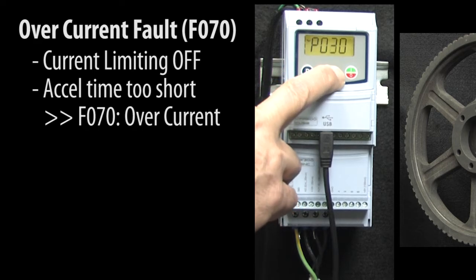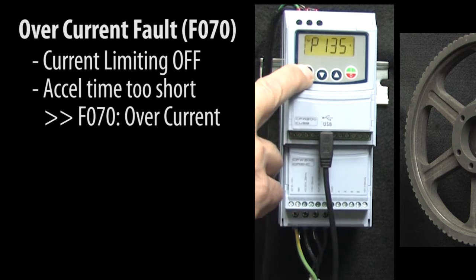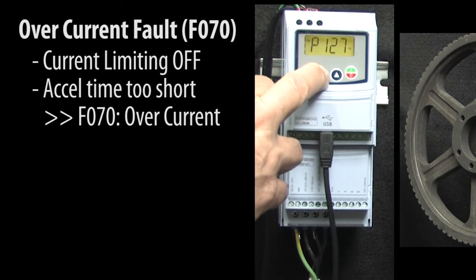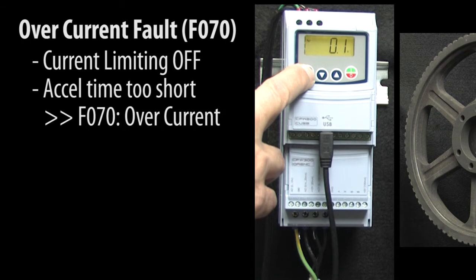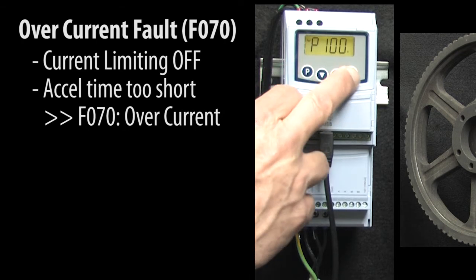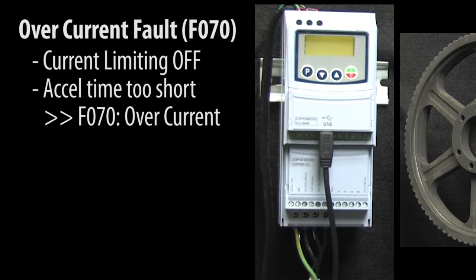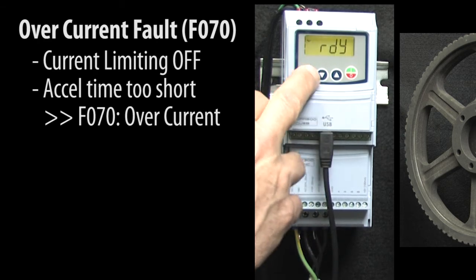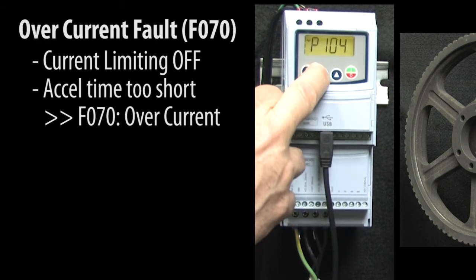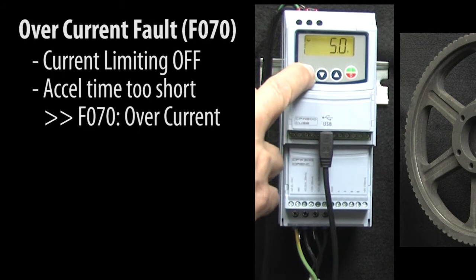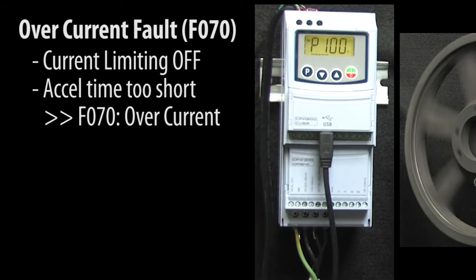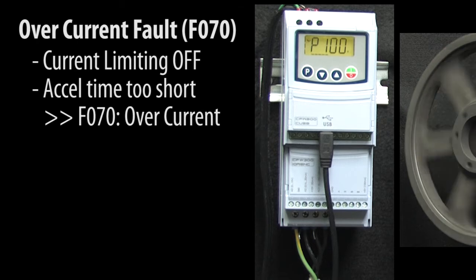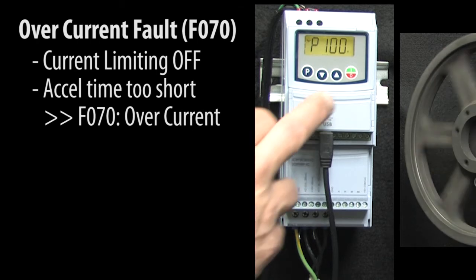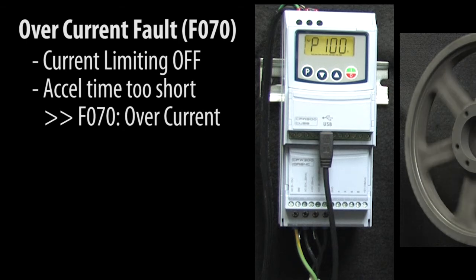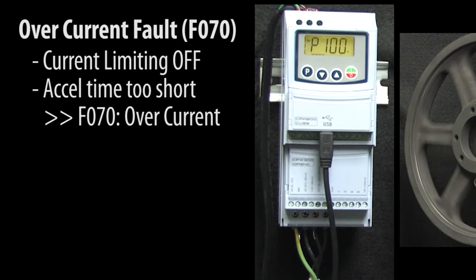I'll go to the current limiting threshold in parameter 135 and set it to a big number, and that will disable current limiting. If we go to parameter 100, we see we still have a really short acceleration time, so that's fine. So I'll hit run, and we immediately get an overcurrent fault. If I clear the fault and extend the ramp time to something reasonable, say 5 seconds, then hit run, everything works great. So if you're getting an overcurrent fault under load, then make sure the current limiting threshold is set to an appropriate value and the acceleration time is reasonable.